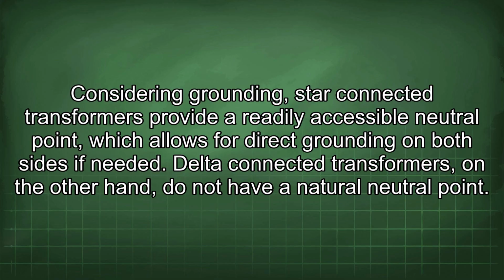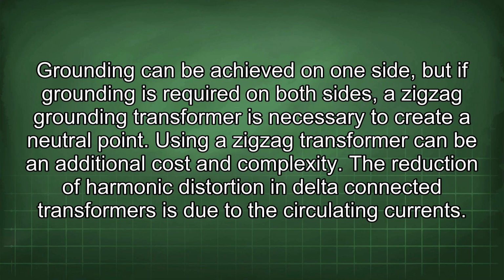Delta-connected transformers, on the other hand, do not have a natural neutral point. Grounding can be achieved on one side, but if grounding is required on both sides, a zigzag grounding transformer is necessary to create a neutral point. Using a zigzag transformer can be an additional cost and complexity.